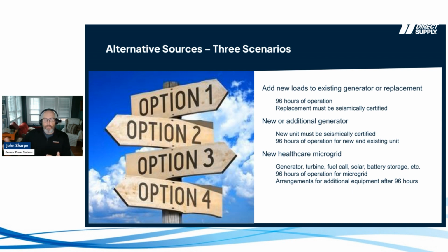Do understand, I'll bring this up a number of times: if you bring in a new generator to take care of these newly mandated loads, recognize that the existing generator still has to be upgraded, or you have to have provisions for 96 hours for that generator too. We can't just run the air conditioning for 96 hours while life safety loads or essential system loads aren't backed up for 96 hours. They both have to be available for 96 hours.